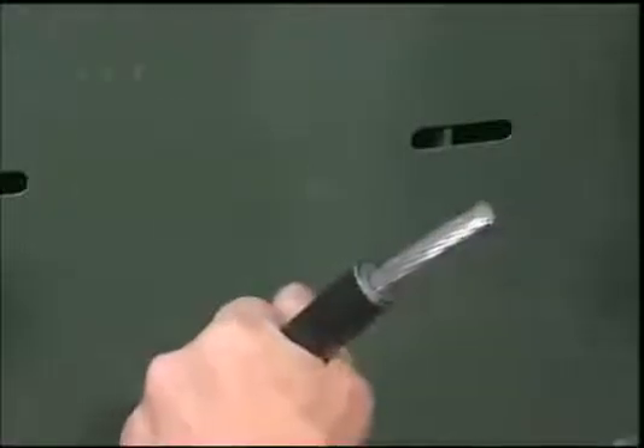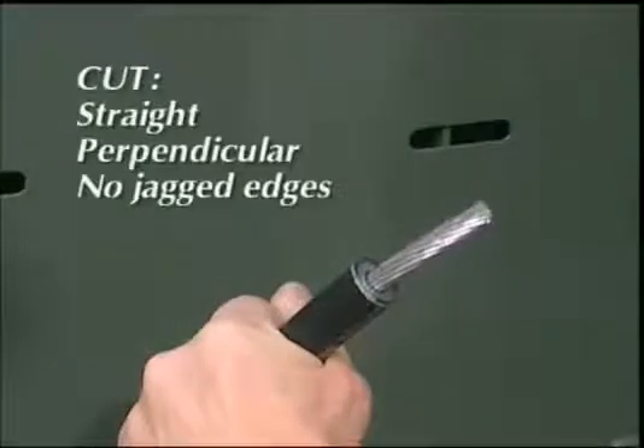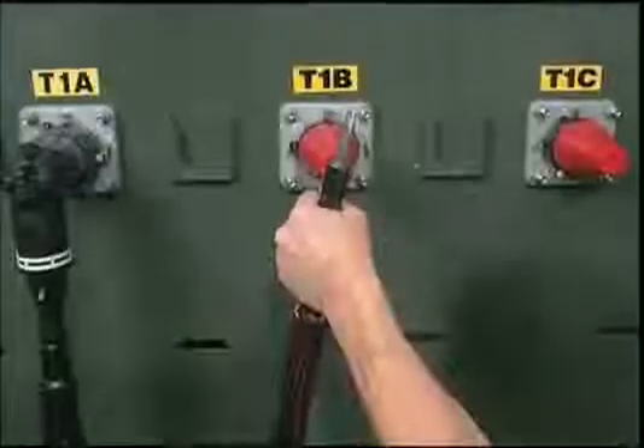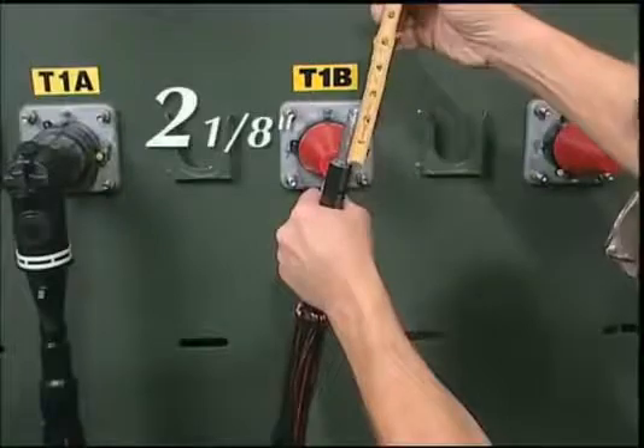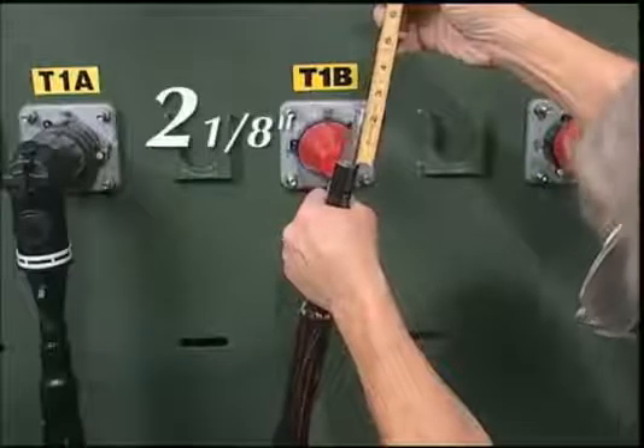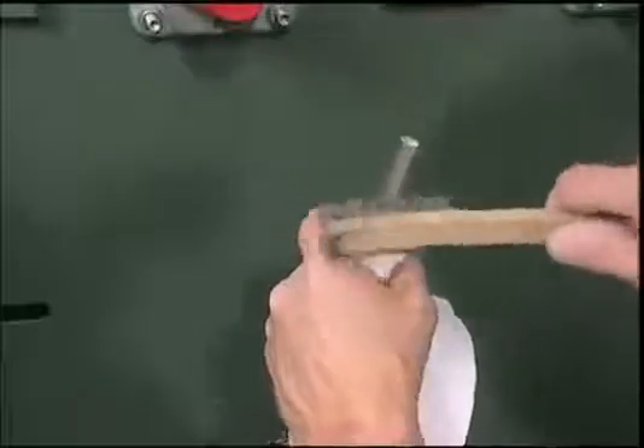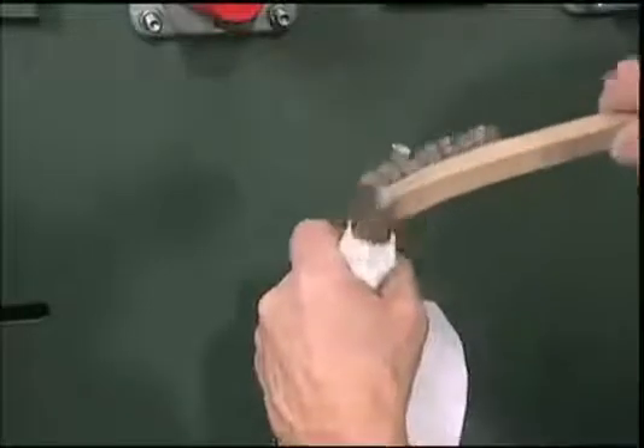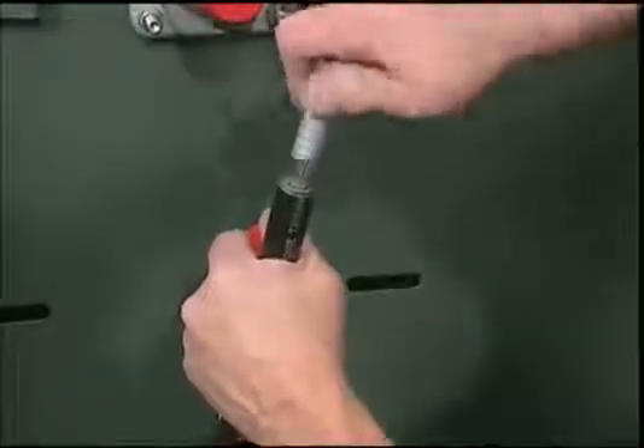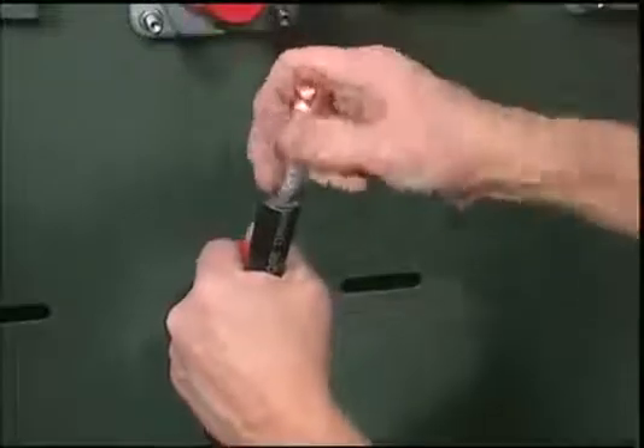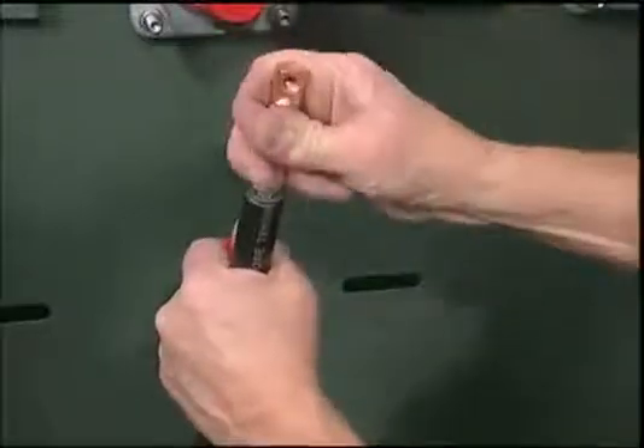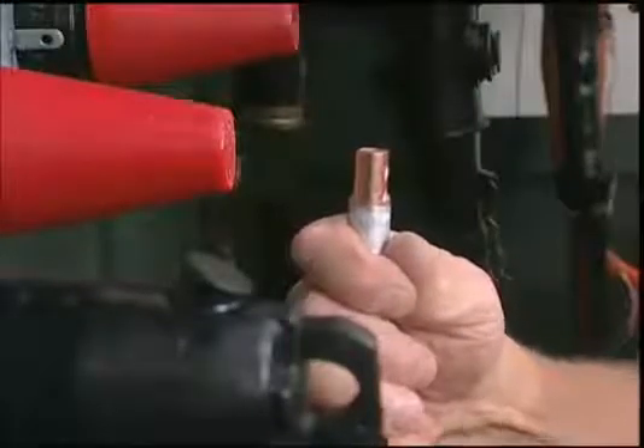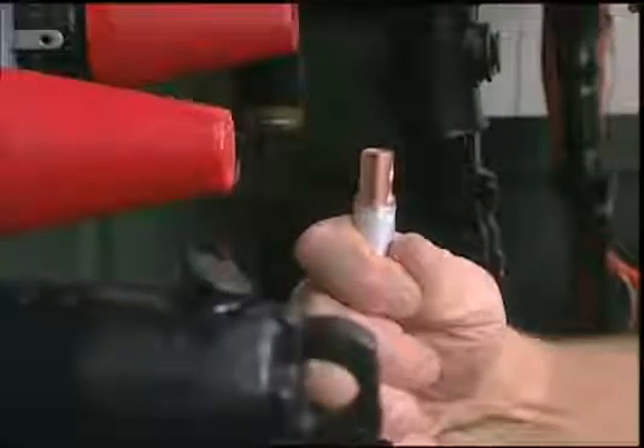Now remove the insulation. When you do this, be sure the cut is straight, perpendicular to the cable, and that no jagged edges exist. Recheck the dimensions to ensure that 2 1/8 inches of the cable insulation were removed. Use a wire brush to clean the exposed conductor. And immediately after, install the copper top crimp connector using a twisting motion to distribute the antioxidant. Make sure the flat face of the crimp connector is parallel to the face of the bushing insert.